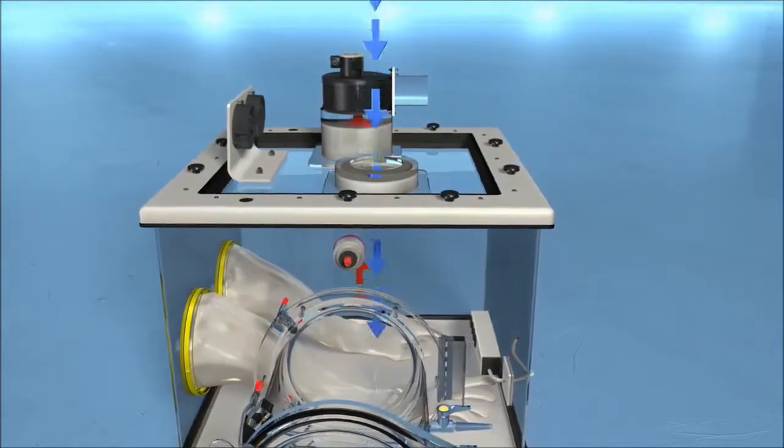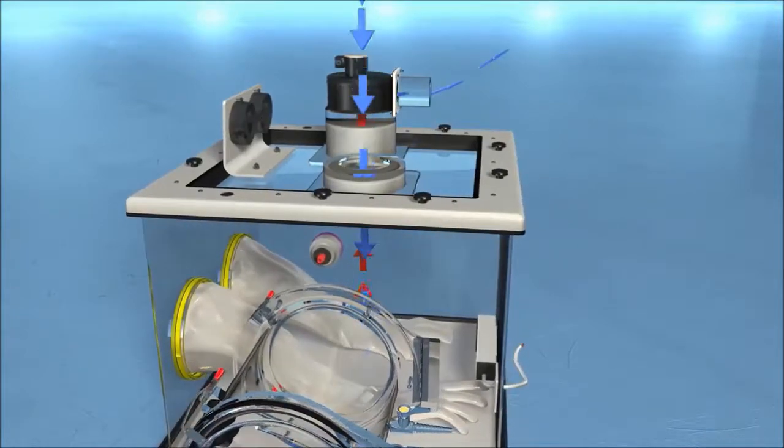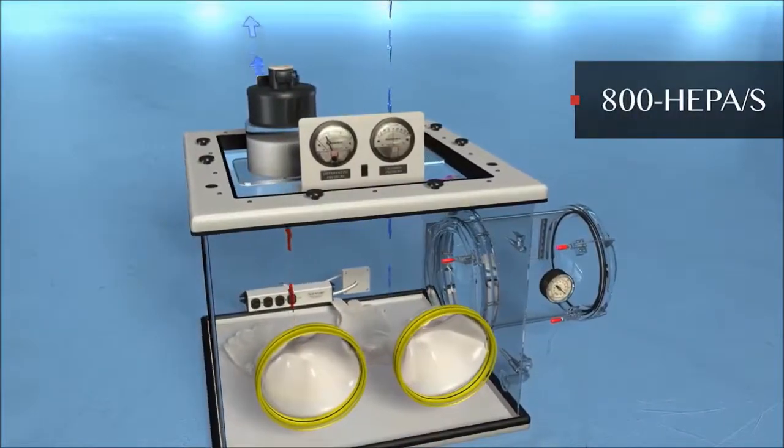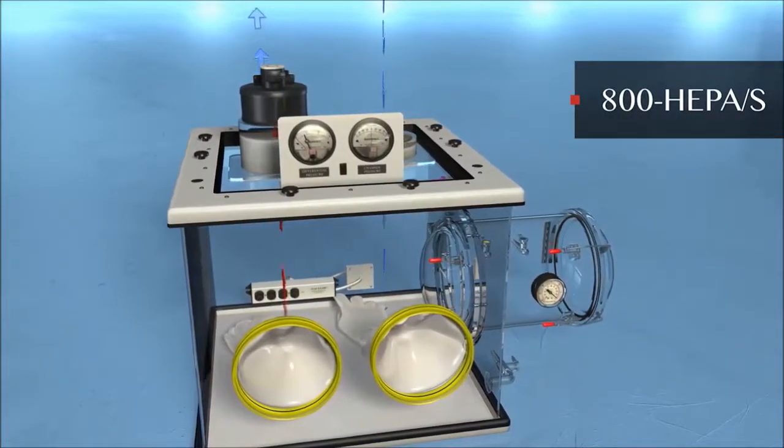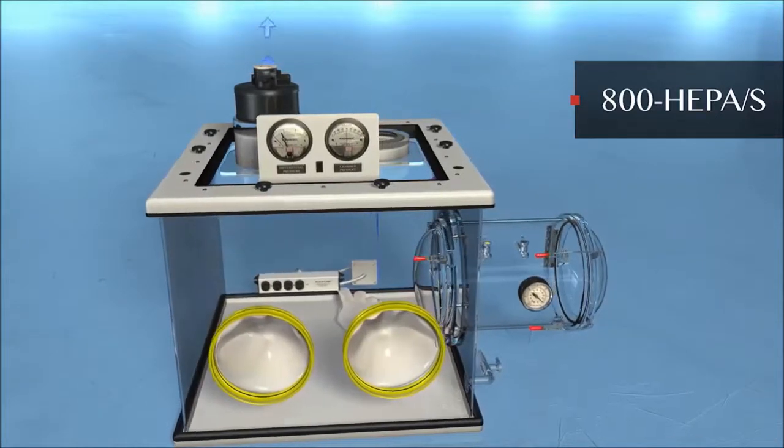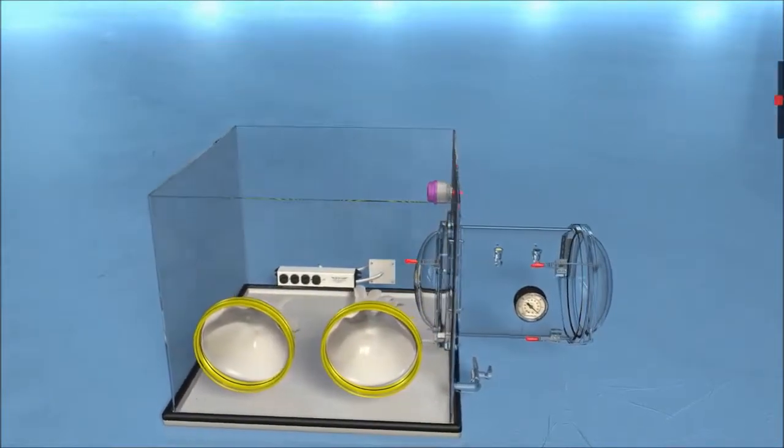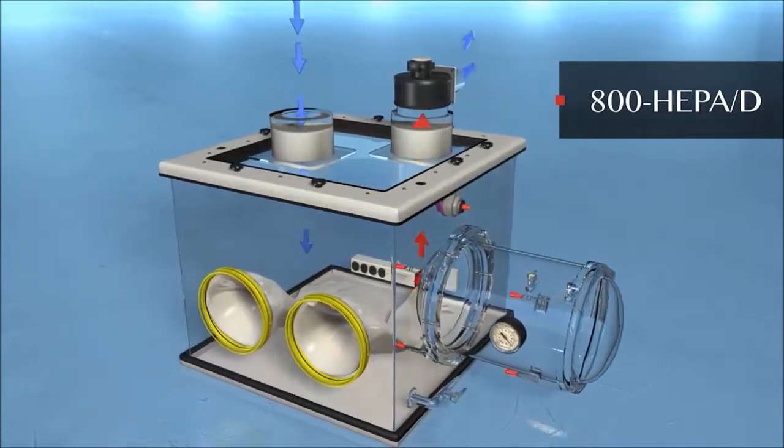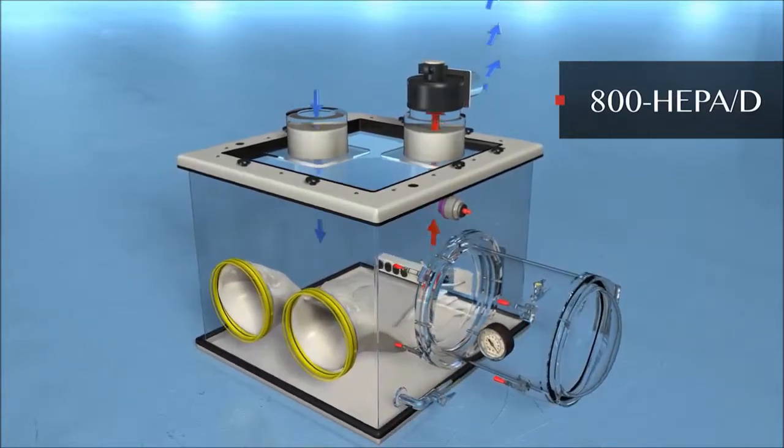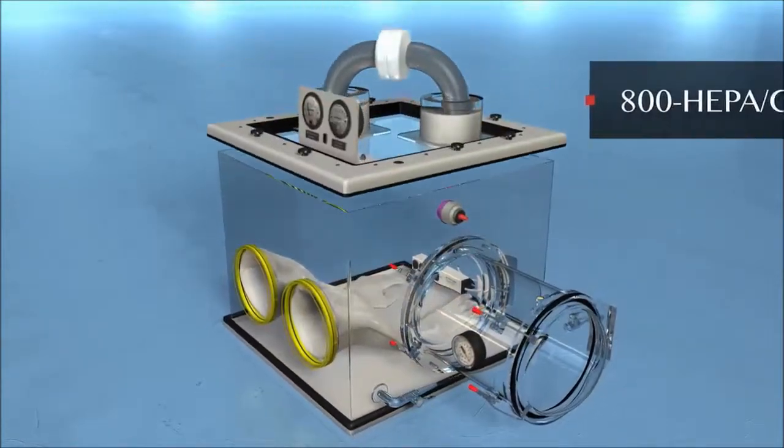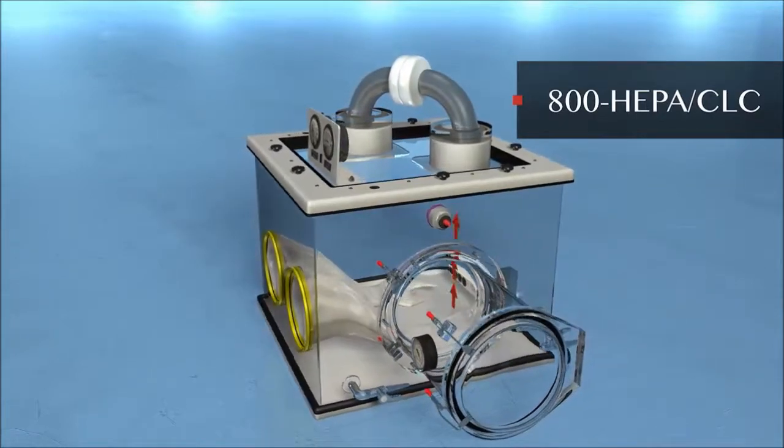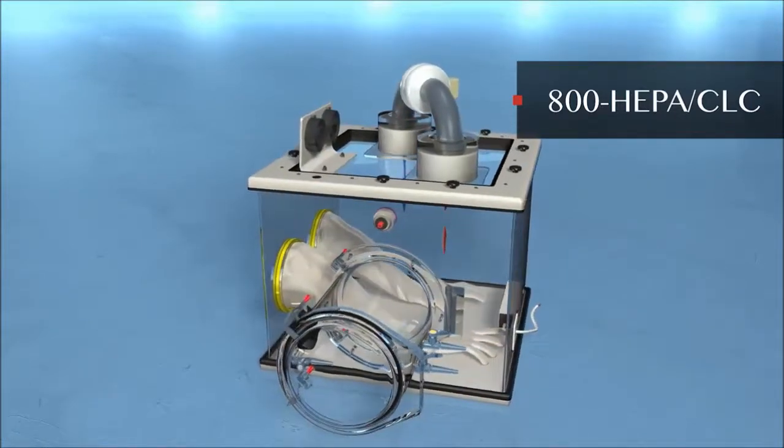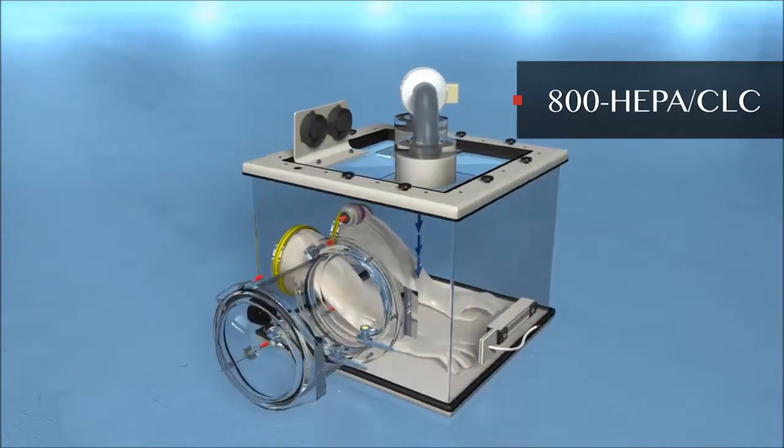Plaslabs offers three types of HEPA filtration setups: 800 HEPA-S single HEPA filtration provides HEPA filtered air into or out of the glove box. 800 HEPA-D double HEPA filtration system: 800 HEPA-CLC closed-loop filtration system continuously circulates the internal atmosphere through two 8-inch round HEPA filters.